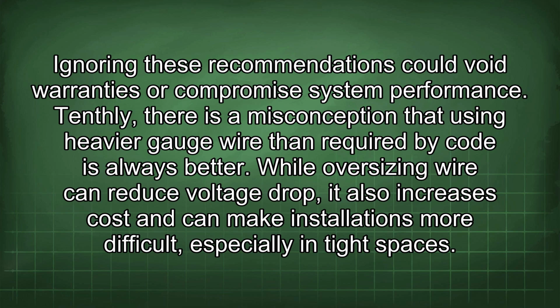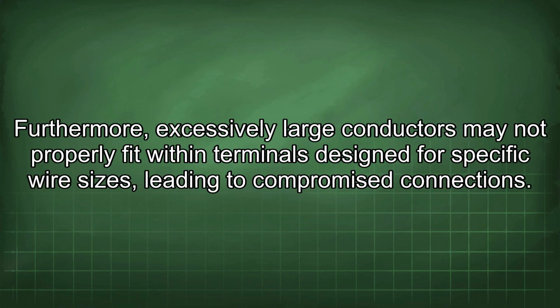Tenthly, there is a misconception that using heavier gauge wire than required by code is always better. While oversizing wire can reduce voltage drop, it also increases costs and can make installations more difficult, especially in tight spaces. Furthermore, excessively large conductors may not properly fit within terminals designed for specific wire sizes, leading to compromised connections.